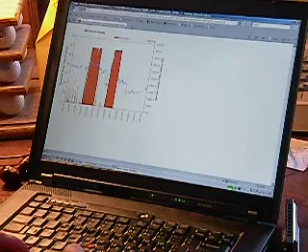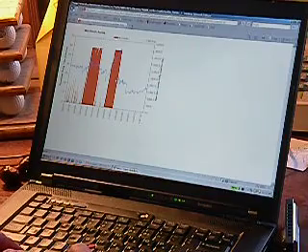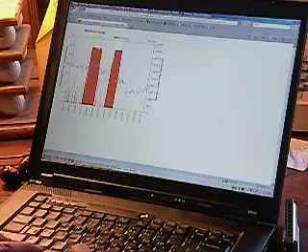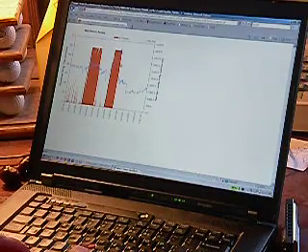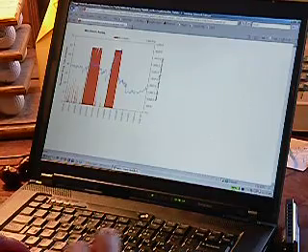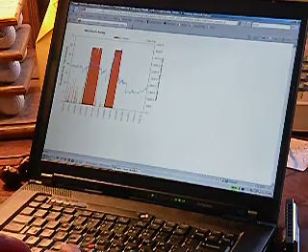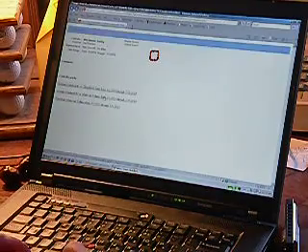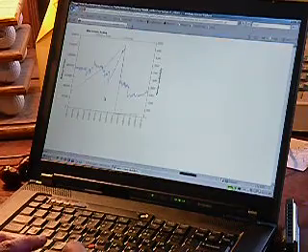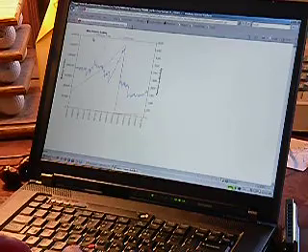So in this case, I happen to know that we had adjusted the outflow of the separator to a point where we weren't getting adequate backflush on the separator to try to control a seal problem. And that turned out not to work, so we corrected the problem here, and everything has been fine since. I used the back button on my browser to get back to the page with the chart links and look at the next chart. Well, this is makeup volume in red, right?